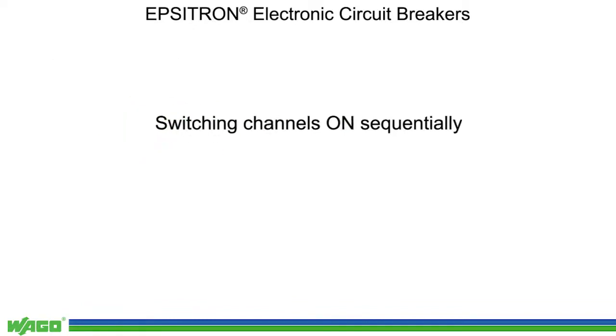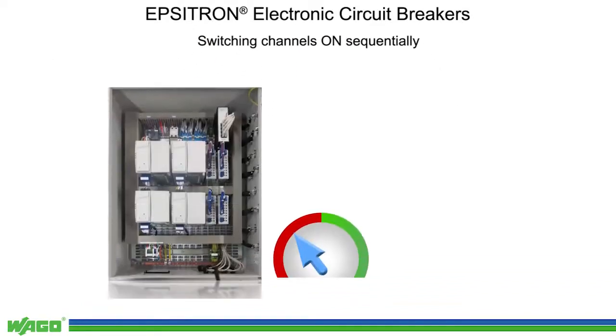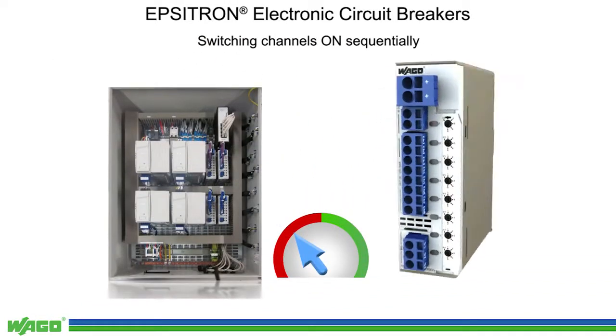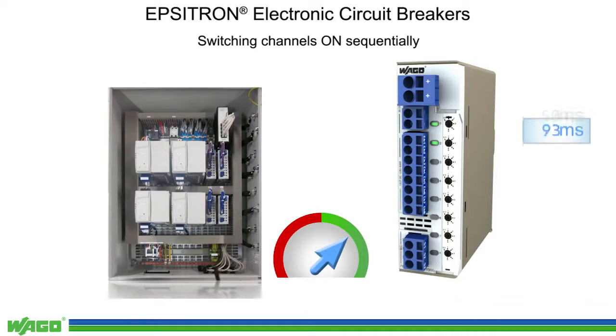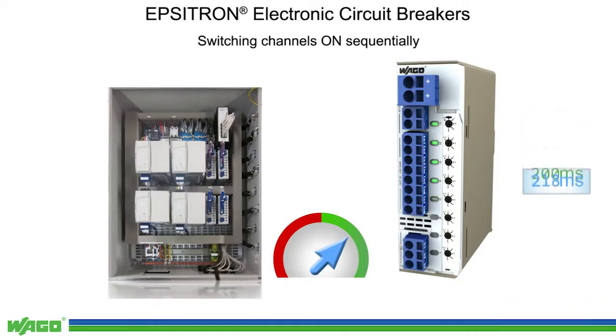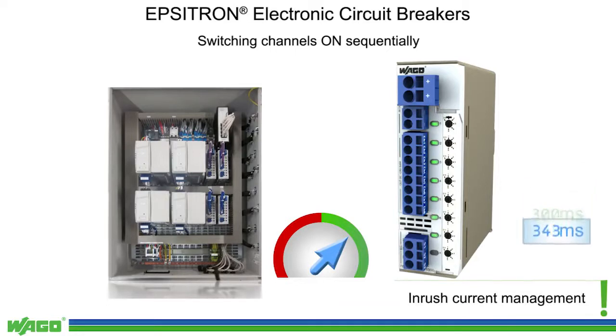Furthermore, WAGO's ECBs provide better inrush current distribution. When an input voltage is applied to the ECB, the device will sequentially switch on the outputs with a delay time depending on the actual current. This eliminates the need to significantly oversize the system's power supply.